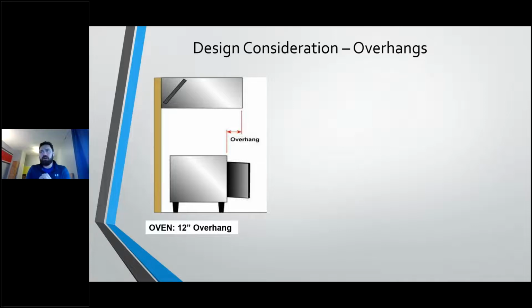A couple other things that I'd like to point out. I mentioned to start that the overhang required per code is a minimum of 6 inches overhang from any exposed side to the hood. To the left or the right-hand side, you would need a 6-inch overhang from the edge of the appliance to the edge of the hood. That holds true for the front of the hood. So code is going to require a minimum overhang of 6 inches. However, I would recommend a best practice of, if you have some sort of a commercial oven, so a combi or a convection oven, that you have an overhang of 12 inches.